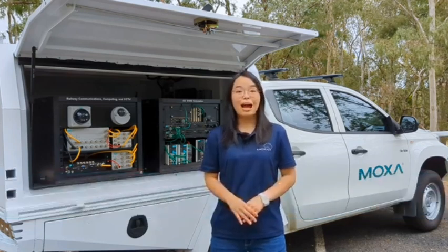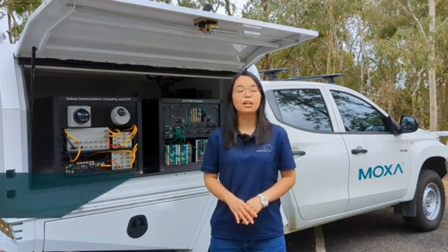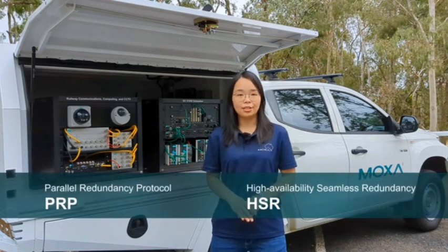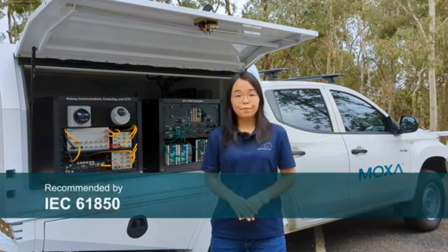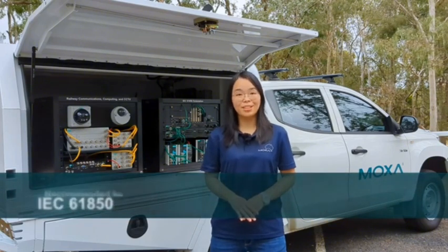In this video, I'm going to introduce two seamless redundancy technologies called PRP and HSR. They are recommended by IEC 61850 for substation automation networks. Communication network redundancy is the key to building reliable automation systems. And recovery time is how we normally measure effectiveness of a redundancy protocol.